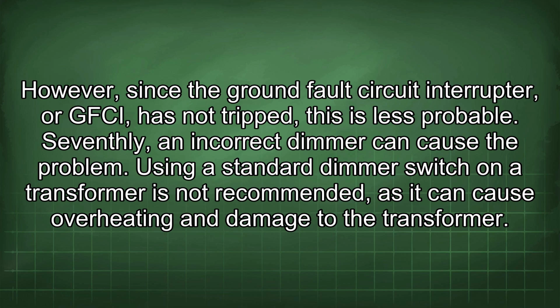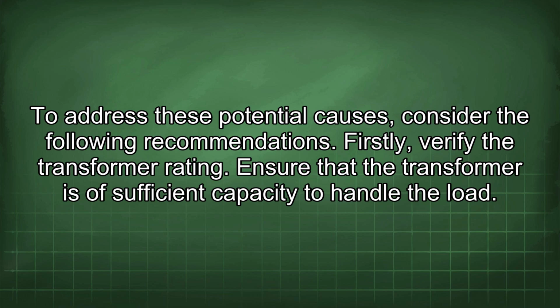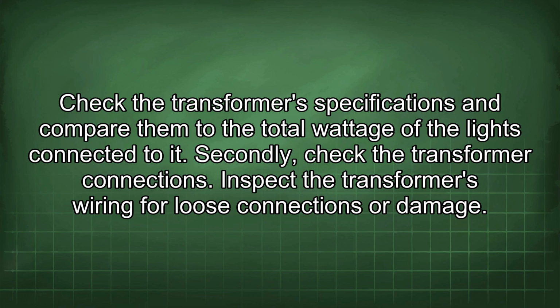Seventhly, an incorrect dimmer can cause the problem. Using a standard dimmer switch on a transformer is not recommended, as it can cause overheating and damage to the transformer. To address these potential causes, consider the following recommendations. Firstly, verify the transformer rating. Ensure that the transformer is of sufficient capacity to handle the load. Check the transformer's specifications and compare them to the total wattage of the lights connected to it.